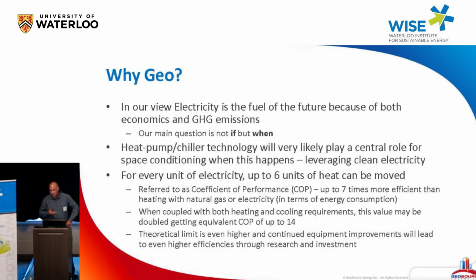Electricity on its own from a heating perspective is horribly expensive, so what we want to do is leverage that electricity use, and that's why we switch to geo, where we use heat pumps or chiller technology to extract heat from the ground in the wintertime and put it in the building, then reverse that in the summer, pulling heat out of the building and rejecting it to the ground, ending up with some sort of balance there.